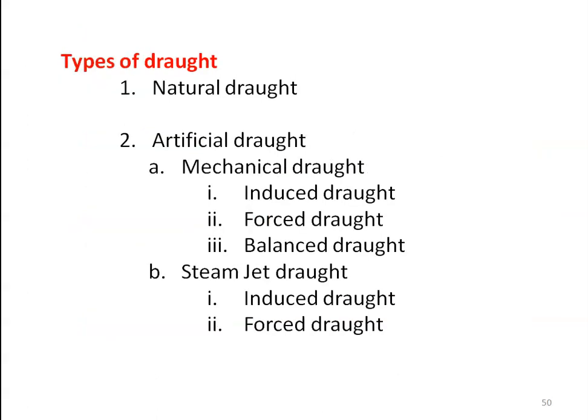There are two types of draught: natural draught and artificial draught. Natural draught is created by the temperature difference of the hot gases and the atmospheric air. Artificial draught is created by a mechanical system. Artificial draught is further classified into mechanical draught and steam jet draught. Mechanical draught is further classified into three types: induced draught, forced draught, and balanced draught. Steam jet draught is also classified into induced draught and forced draught.